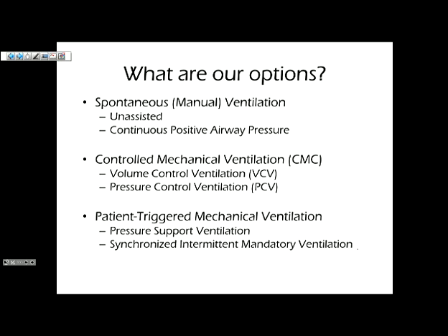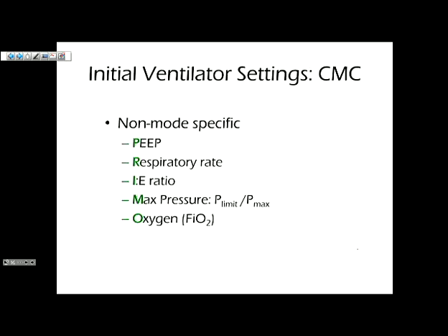So we're going to dive in first to those controlled mechanical ventilation modes. And again, they're time-triggered, time-cycled. That's where we're going to spend a lot of our time. These other parameters are non-mode specific. Regardless of the mode that we might be using, we have to set these other things, and we've started to talk about some of these things.